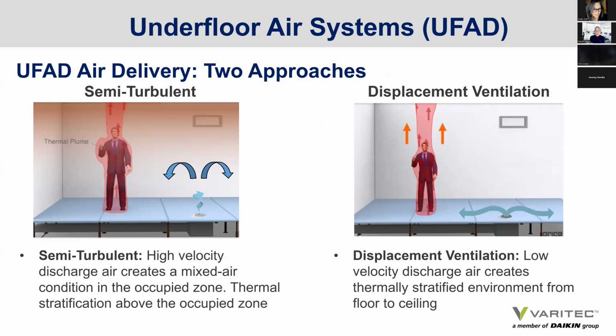There are two air delivery solutions for underfloor air. There's a semi-turbulent design that injects air about 5 feet into the occupied zone and creates a semi-mixed air condition within it. And then thermal stratification from an occupant removes that contaminated warm air to the upper level of a room. So a mixed air underfloor system supplies more air through each floor device to create a higher velocity discharge.